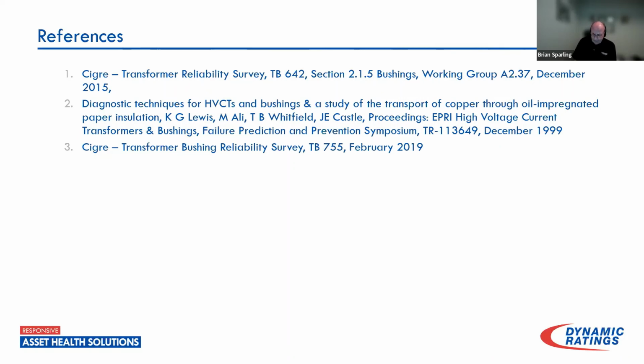And understand that the results of that often come up with what I call the total available total moisture inside the solid insulation system of the bushing and/or transformer. So it is a far more sensitive test, but it is an offline test, and more people are doing it. It's also shown that things may look perfectly reasonable at the fundamental frequency of 60 hertz or 50 hertz, depending where you are, but the insulation system could be deemed wet when you look at the rest of the data coming out of that sweep frequency testing.